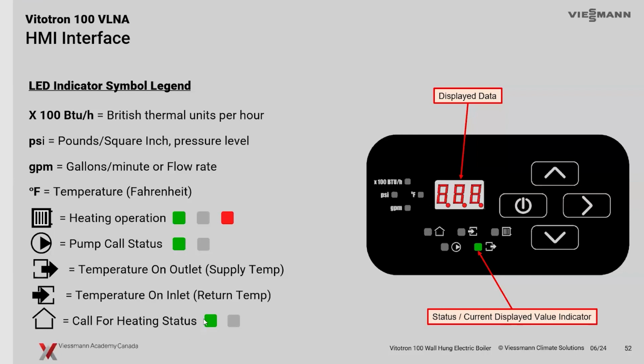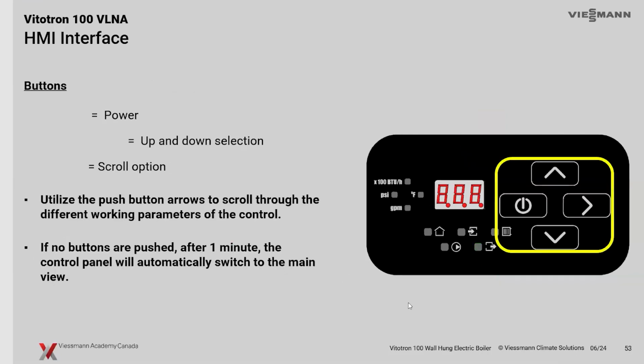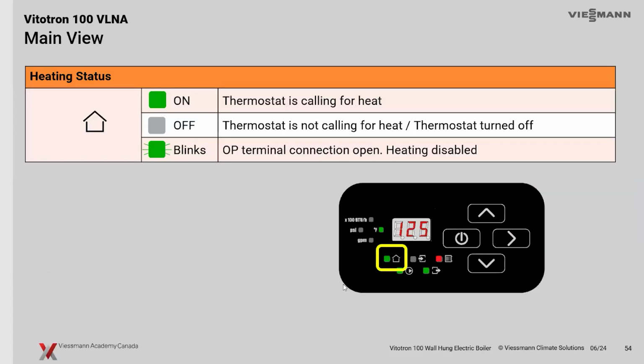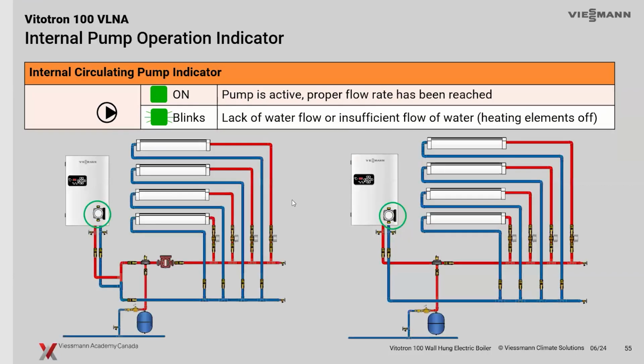Now, if we've got a call for heat and our OP is on, this status will give us a different type of symbol to let us know that we got the call, but right now we're being blocked because the OP terminal is open. So we use these navigation screens here. If I'm looking at my system, there's my call for heat. If it blinks, the OP terminal is open. So it's telling me that, yes, you've got a call, but you're being blocked because you're waiting for electricity rates to change. We've essentially opened that contact. So it gives you a good idea that your heating is disabled, even though you have a call.